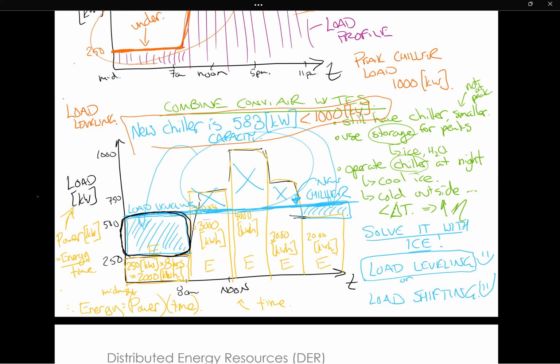In this time, you are running your chiller, look at my chiller, this blue line. You just keep running it, keep running it. Is it better for your chiller? Absolutely, there's no maintenance issue from a chiller starting up and slowing down. You are running it at a constant capacity.